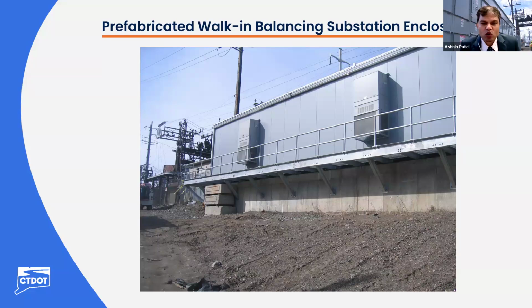The recent construction technology is moving away from building a brick and mortar building, which will require a lot more labor work at the job site. The balancing substation manufacturer would have to send each piece of equipment right to the job site, and it will create delay in the project construction. So the overall cost would increase. So this is the reason the balancing substation would be much easier to fabricate at the balancing substation manufacturer's factory.